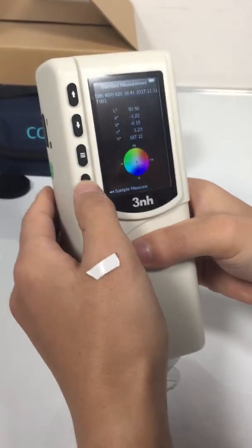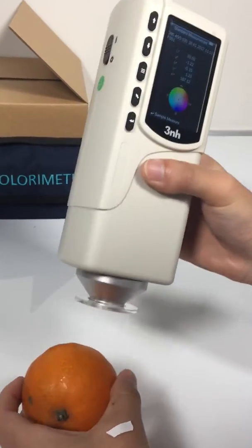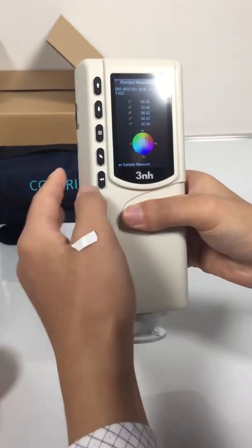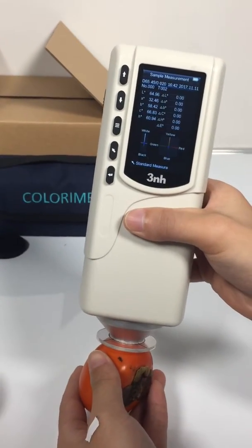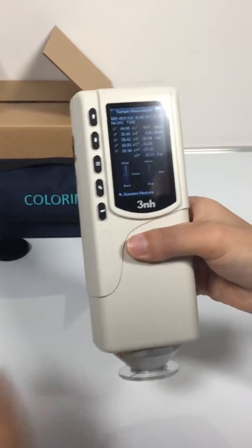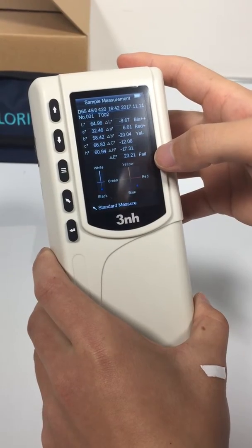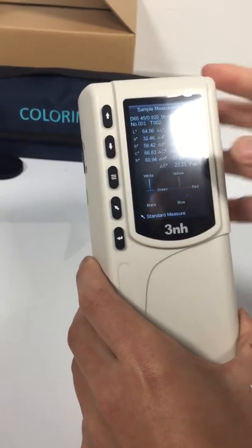Now it's ready for measurement. Measure standard first, and then measure a sample. These are the test results. This is a color offset indication, and this is a test result judgment. The delta E is too large, so it shows fail here.